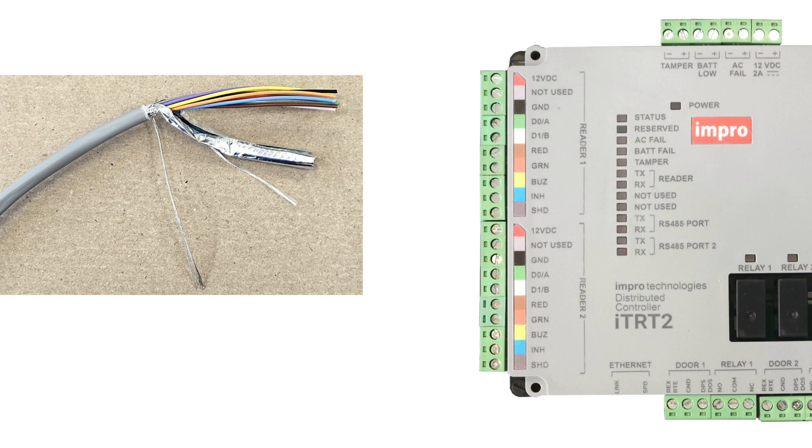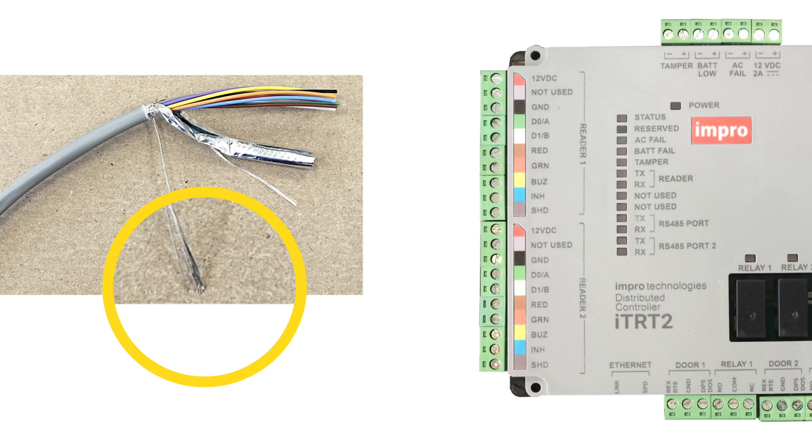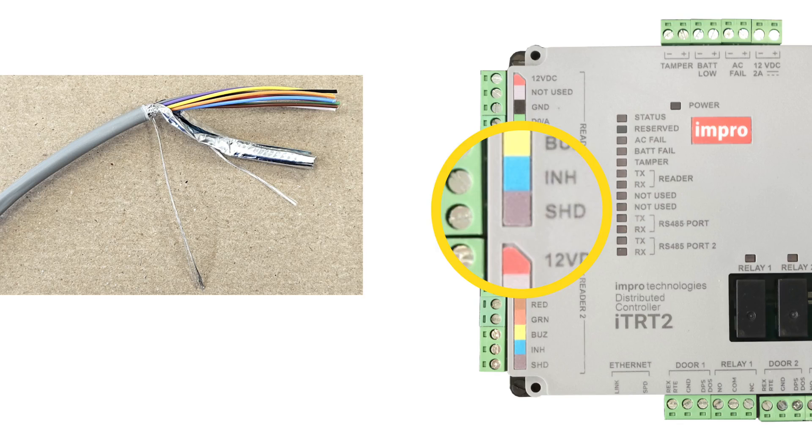The effects of electromagnetic interference can be reduced by connecting the data cable screen to the SHD terminal only on the iTRT2 end of the cable.